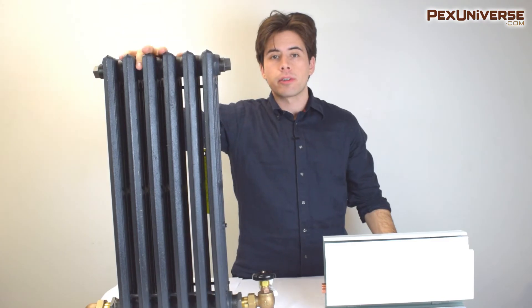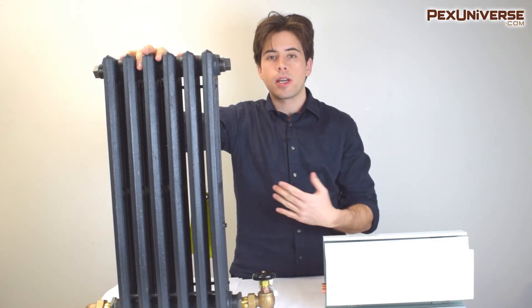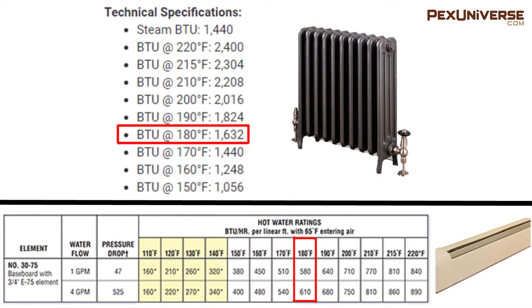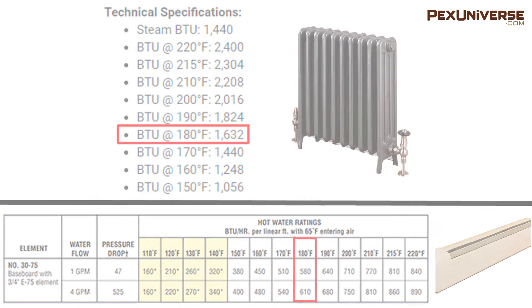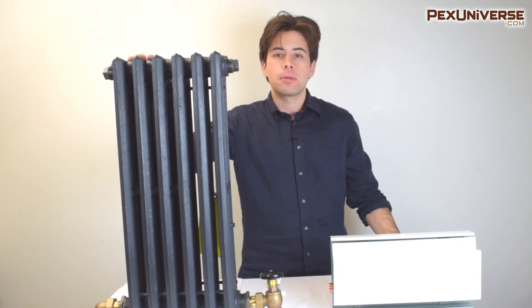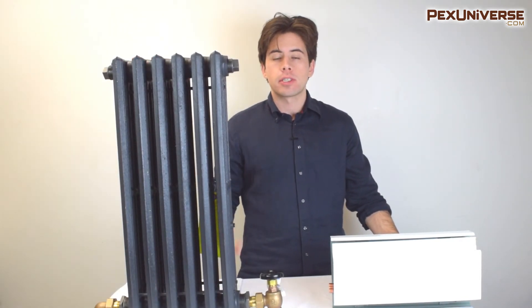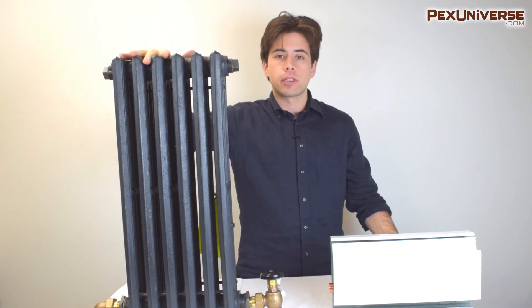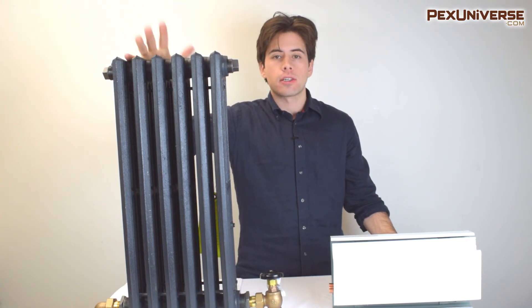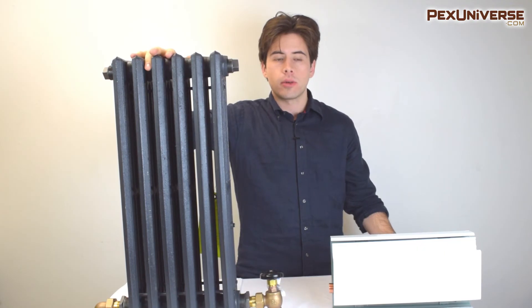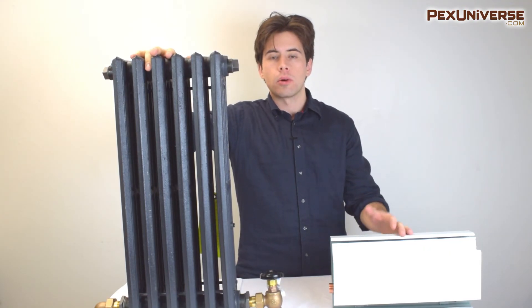The most important point about efficiency can be expressed in BTUs. With a standard heat supply line of three-quarter inch at 180 degrees Fahrenheit, a six-section cast iron radiator has a BTU output of 1,632, while baseboards have about 600 BTU output per foot. With the same supply input, the radiator is about 63% more efficient. Additionally, you can use steam heating with radiators, whereas you can't with baseboard heating or forced air heating.